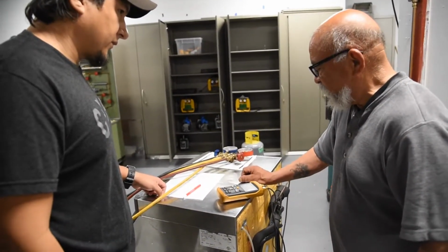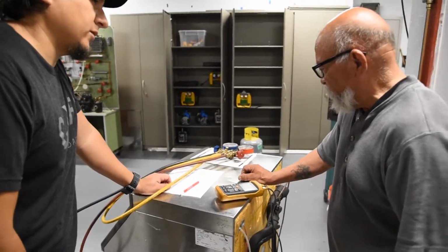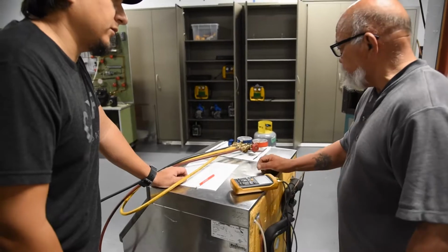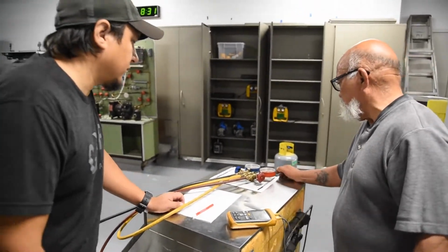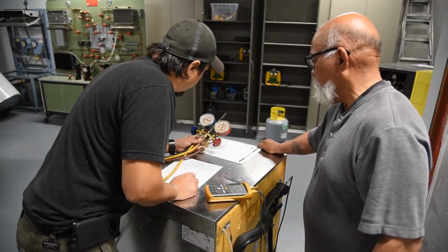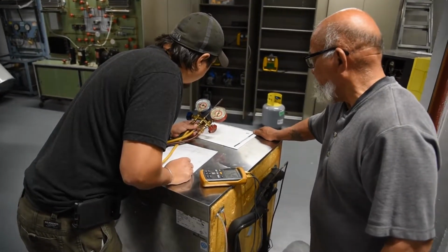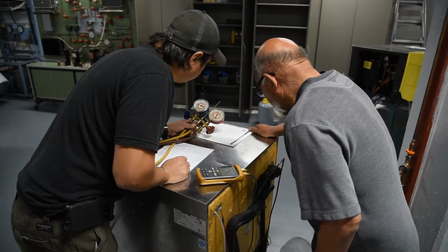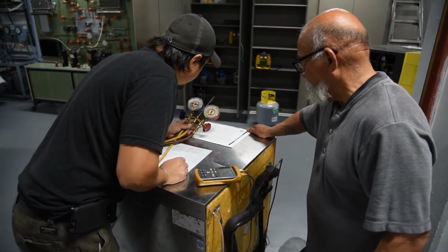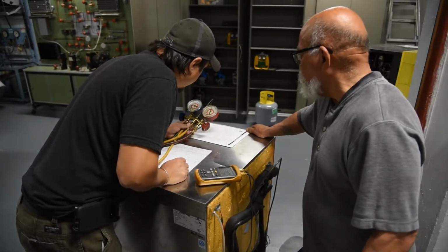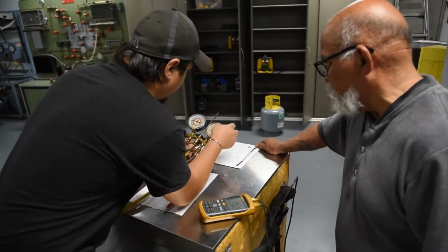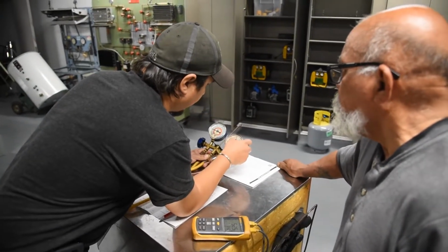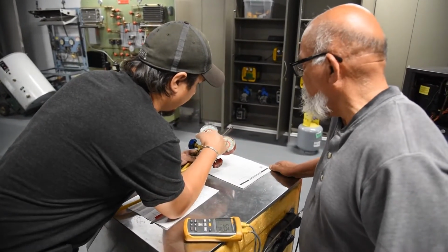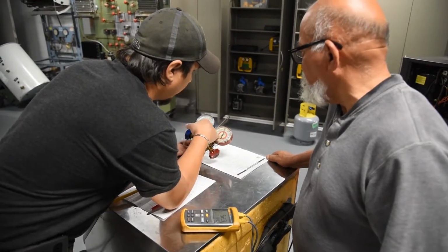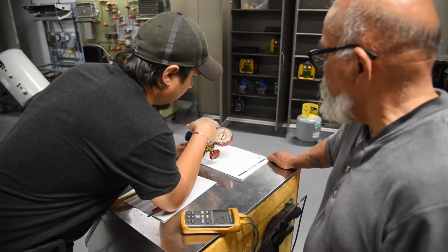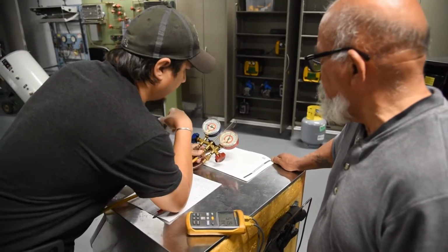We just went through a harvest. It's going back into ice making, and the pressure on the high side, what's that? Right now, it's above 300. It's 310, and the temperature is 110. How do you know the temperature of 404? It has a PT chart right here integrated to the gauge. Okay. So the orange part right here is specifically for 404A. Correct. So I can just read the needle between the PSI and the PT chart integrated into the gauge.